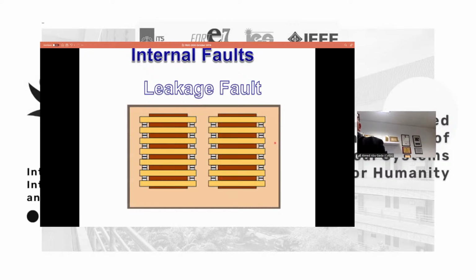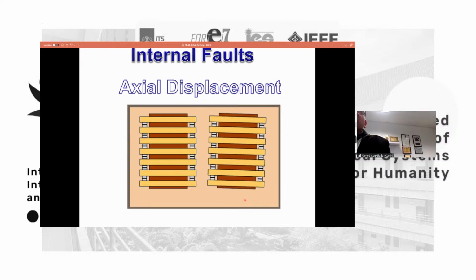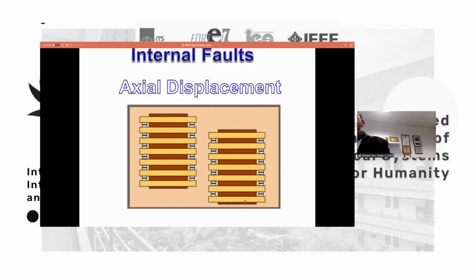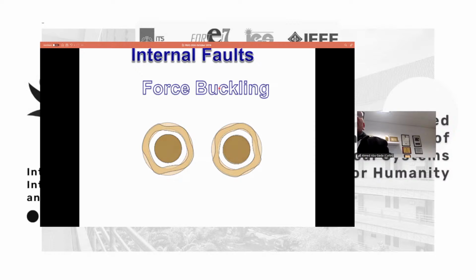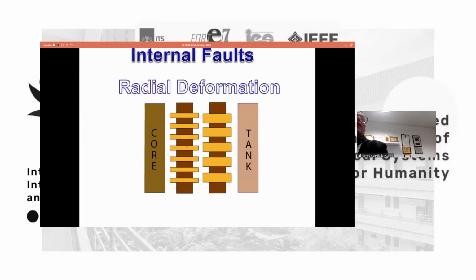Leakage fault is coming from the oil. If you lose the dielectric ability of the oil, you may have some leakage current coming from the winding to the tank outside. Axial displacement: when you have huge electromagnetic force on one winding, you have two components, one upward and one downward. If they are not equal, you may have a movement like that. Buckling, forced buckling: again, the electromagnetic force could be in the radial direction, causing buckling like that. And you have seen that in the first 2 or 3 slides. Or radial deformation, when your internal winding moves onward to the core, causing core deformation.